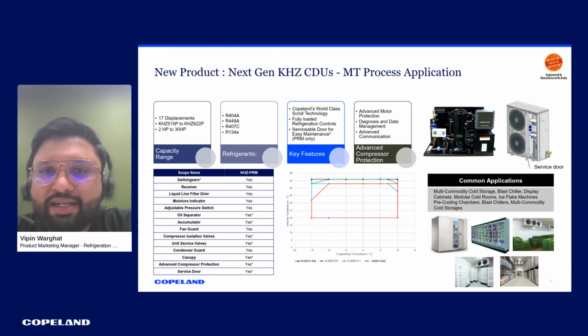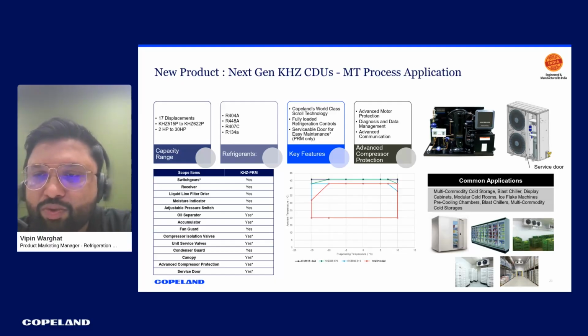Yeah, so this is the condensing unit. It's available from 2 to 30 horsepower. It has fully loaded refrigeration controls. It comes with advanced motor protection for higher capacity models. It has a serviceable door. It can work with multiple refrigerants. So tomorrow, if any refrigerant is getting banned, you don't have to change the entire unit. You just change the refrigerant. All temperature applications can be handled through this condensing unit, and these are purely made in India. So if you go to the next one.